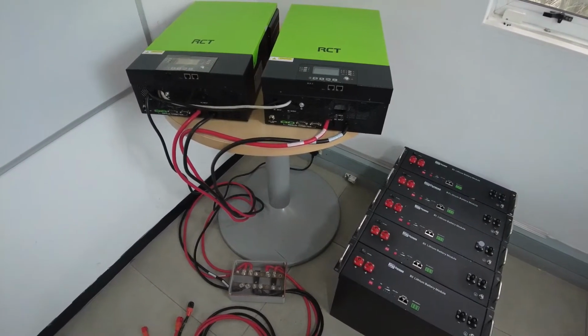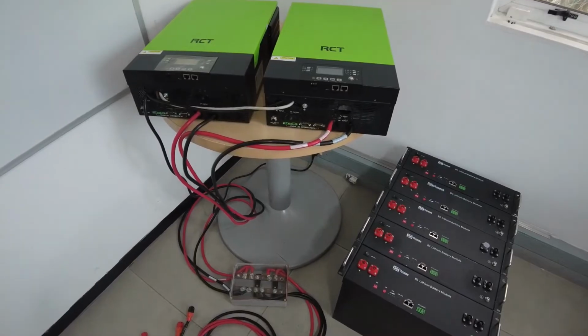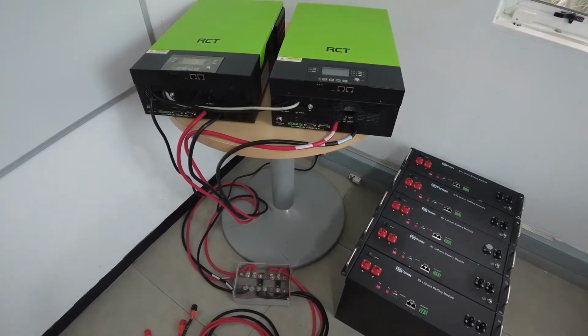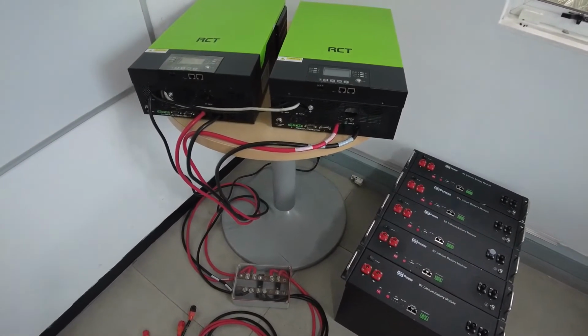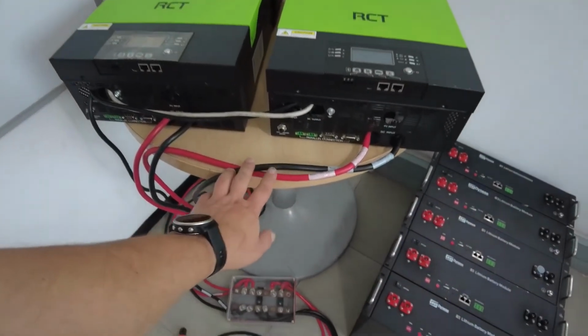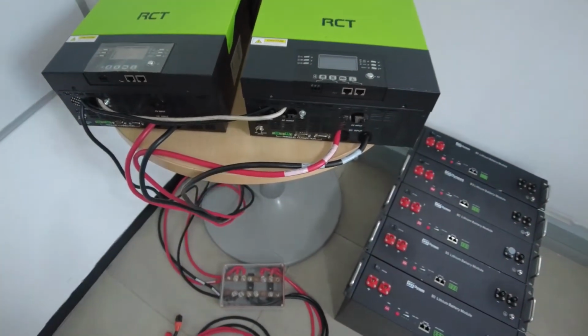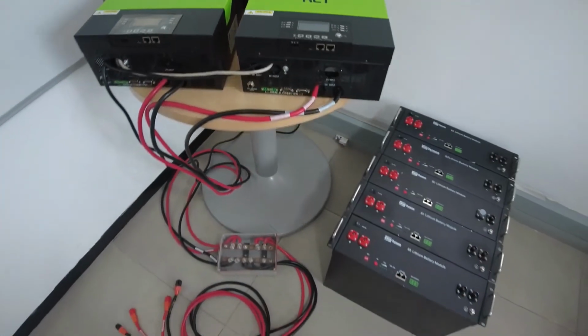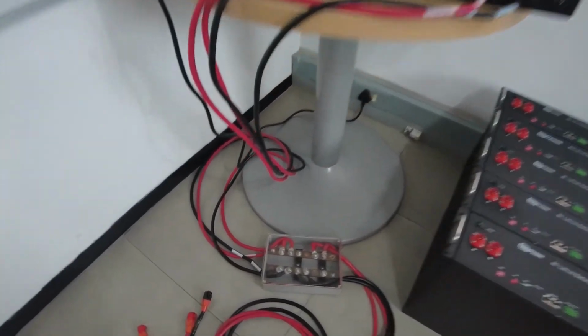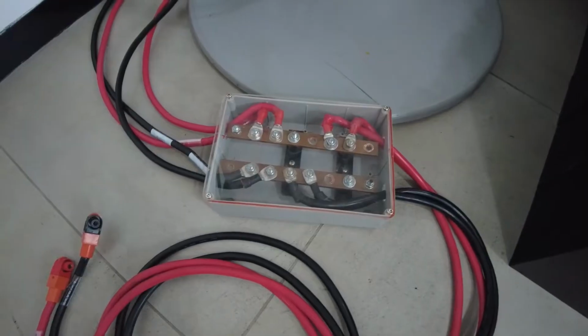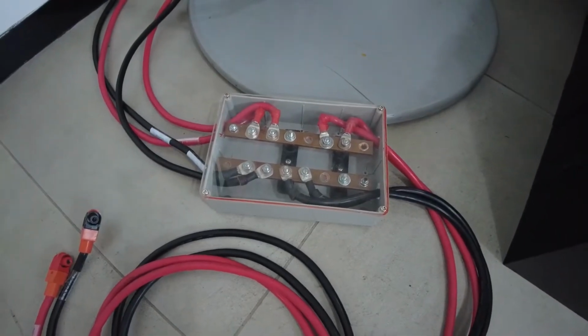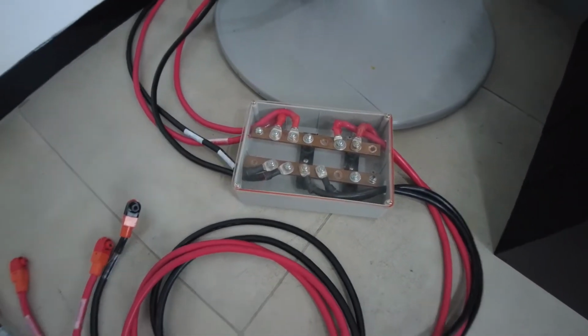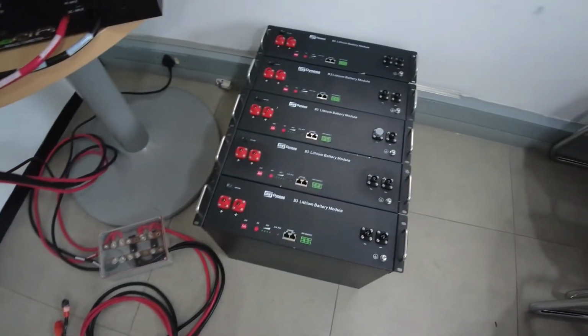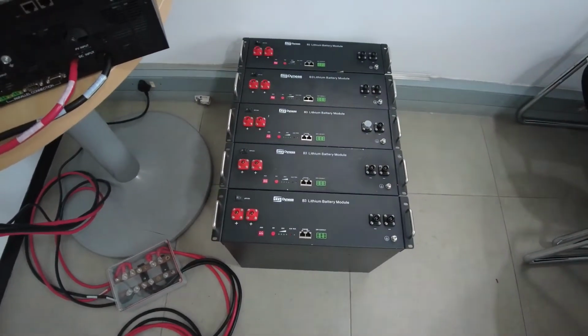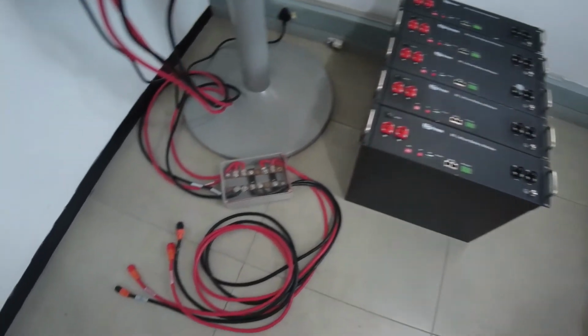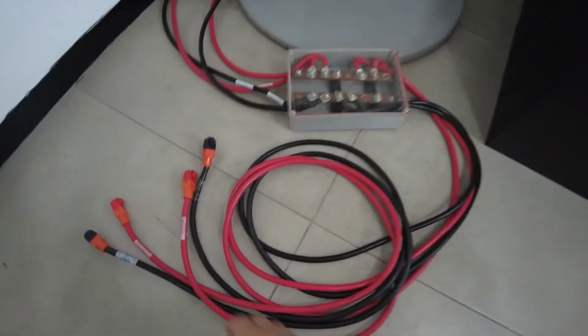Now generally if you go up to bigger inverters, like the 8 kVA, then obviously your cable thickness might be a problem. So generally it will be better to use a combiner box, bus bars, to do all of your connections. It is the same when you connect multiple batteries. Your load is just too much for a pair of cables.